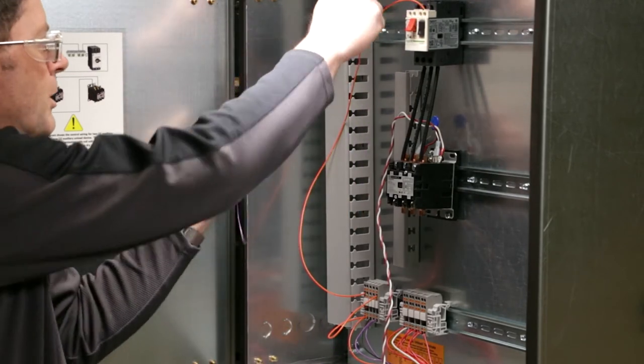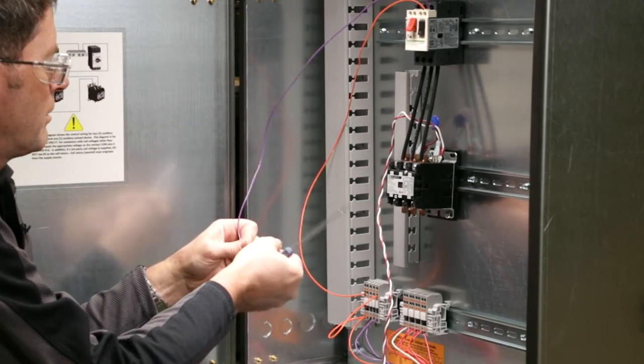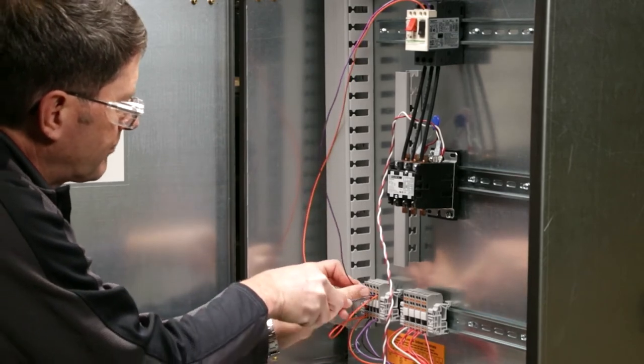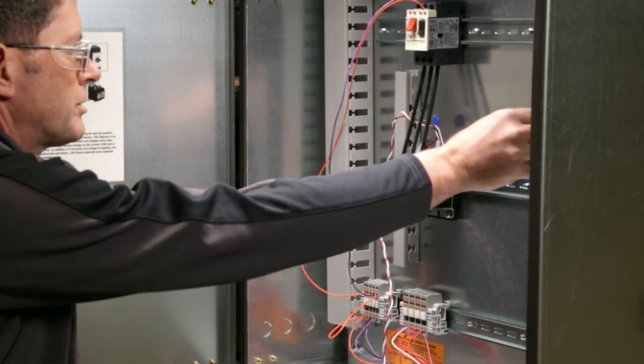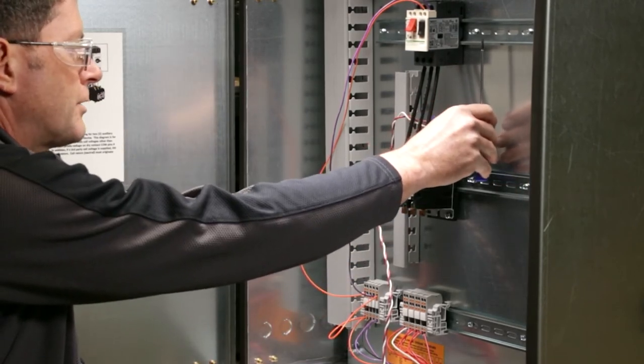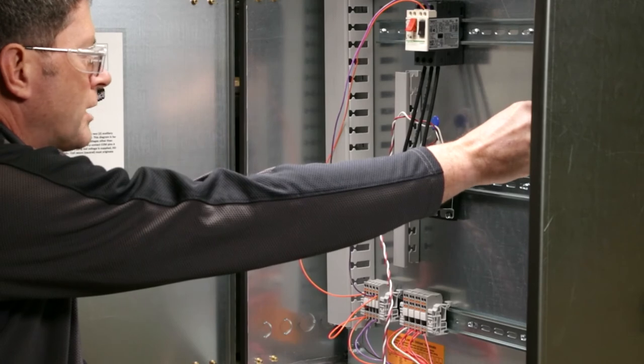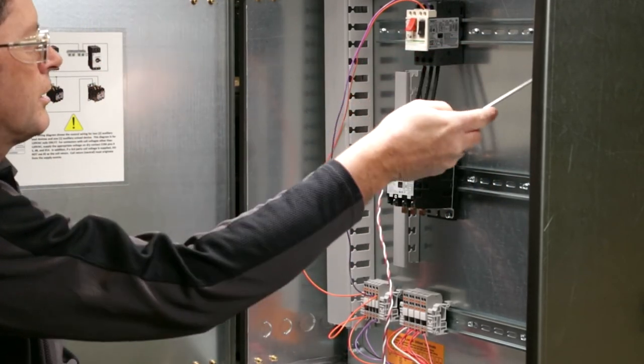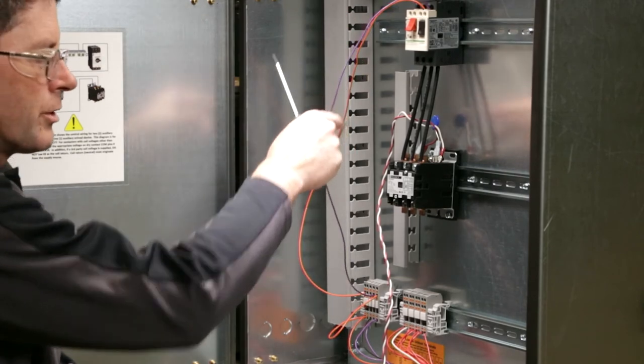And then we'll need to have another wire supplied to return that signal back to our circuit 49D. If you add additional contactors in here, you could have an additional load contactor and a takeaway contactor. You would simply need to wire those in series with the final one returning on circuit 49D.